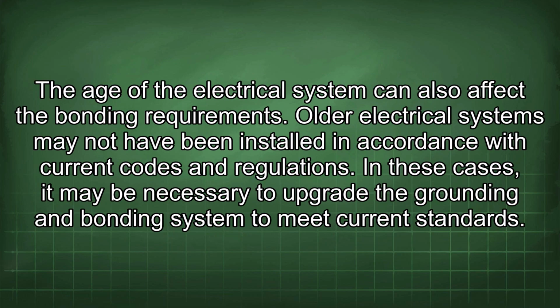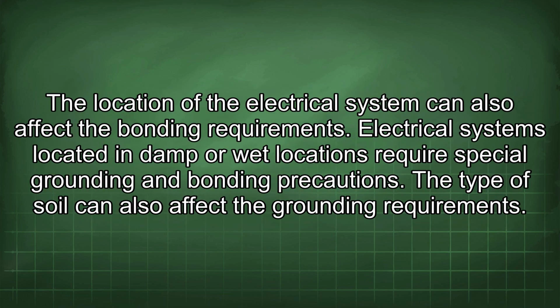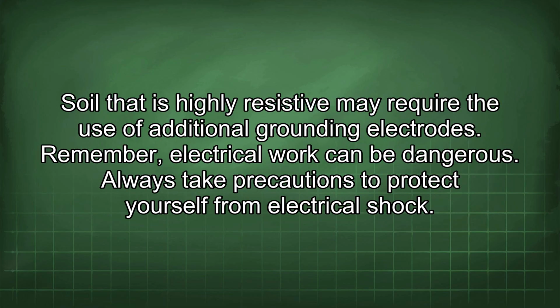The age of the electrical system can also affect the bonding requirements. Older electrical systems may not have been installed in accordance with current codes and regulations. In these cases, it may be necessary to upgrade the grounding and bonding system to meet current standards. The location of the electrical system can also affect the bonding requirements. Electrical systems located in damp or wet locations require special grounding and bonding precautions. The type of soil can also affect the grounding requirements. Soil that is highly resistive may require the use of additional grounding electrodes.